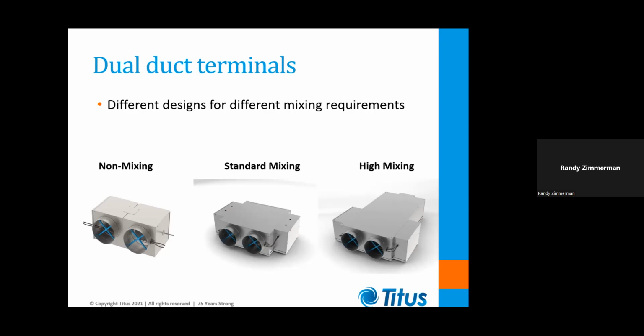Sometimes people are confused by why there are so many different models. It's based on the type of mixing they provide. If you just take two single duct boxes and screw them together, that's a non-mixing box. That means they're not designed for mixing hot and cold air together. One damper is going to be closed while the other one modulates. So that's your heating or your cooling box. Then you've got the standard mixing box that gives you a 1:10 mixing ratio, which is standard in the industry. And then some really fussy universities want a 1:20 mixing ratio and will opt for the high mixing box, which is physically larger and more costly.